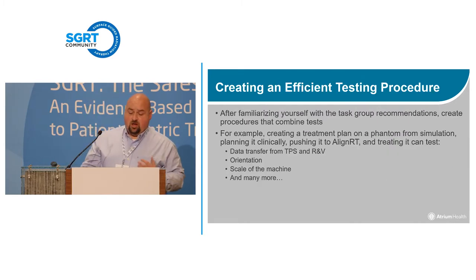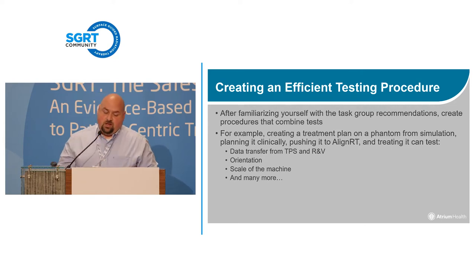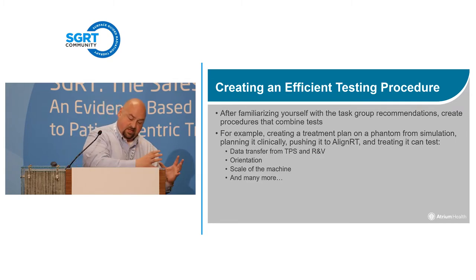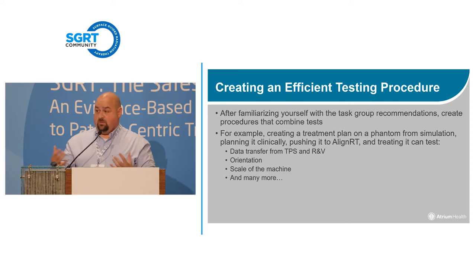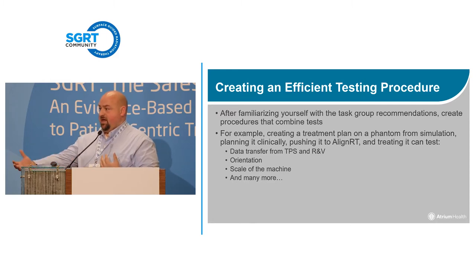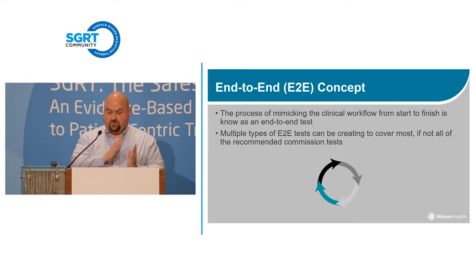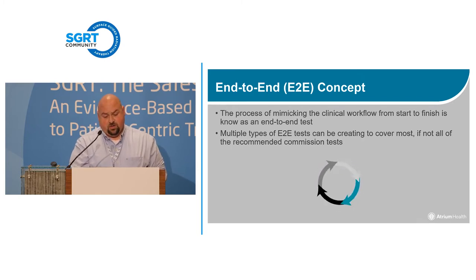A quick rundown of what TG-147 says: check integration, spatial reproducibility and drift, localization, and documentation. What's the best way to create an efficient procedure? You can combine tests in a way that makes sense, and that's where end-to-end testing is so important. You can create a test to check the sim, transfer orientation, and verify machine scale. We actually went through a scale change on two of my IX machines recently and had to adjust the AlignRT software to account for it.